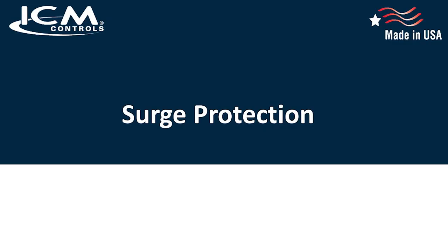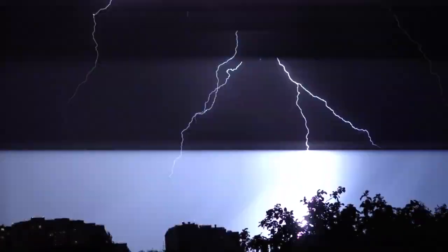Surge protection. What is the difference? And why do you need a surge protective device if you already have a line voltage monitor protecting your equipment? Because line voltage monitors can't react quick enough to defend against a sudden surge or spike that comes through the power line, usually caused by a lightning strike.